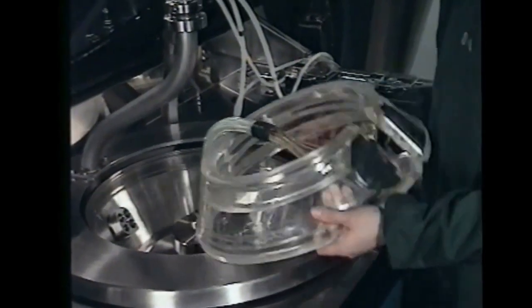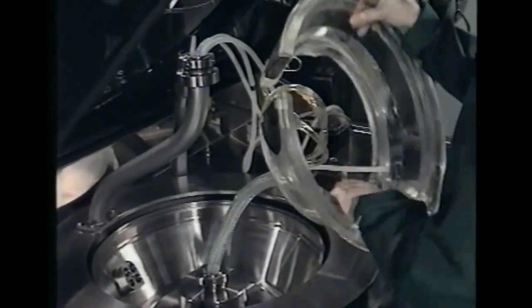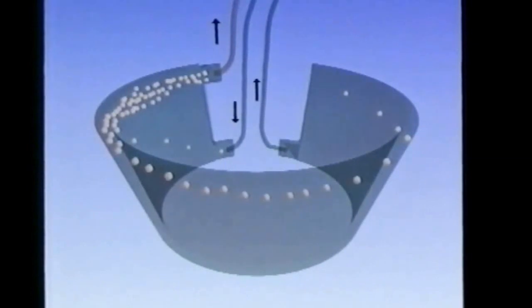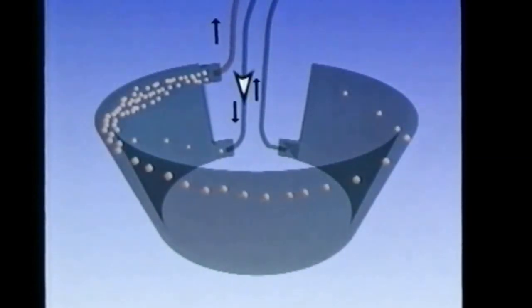The bladder sits on a conical-shaped support ring which is clamped into the separation rotor with a locking ring. The cell suspension is fed into the inlet at the bottom of one end and the clarified liquid is drawn off from the outlet at the bottom of the other end.